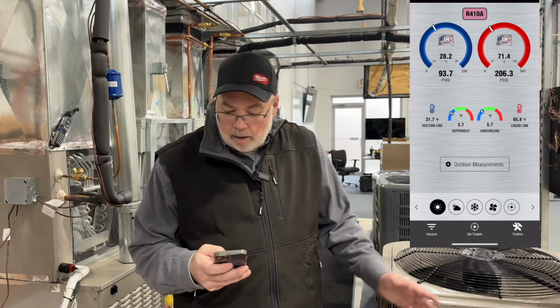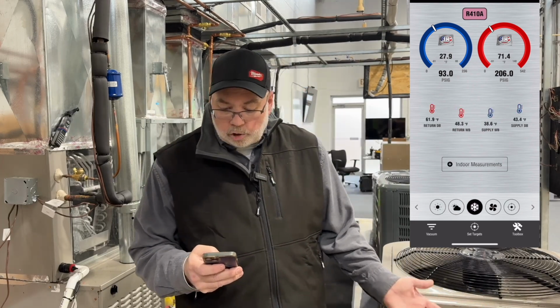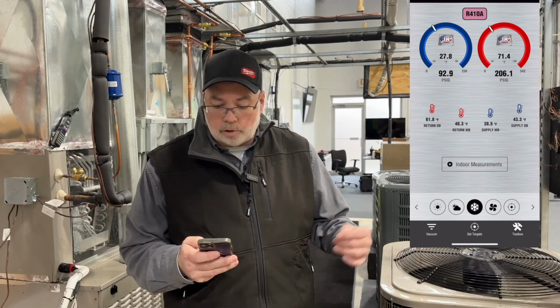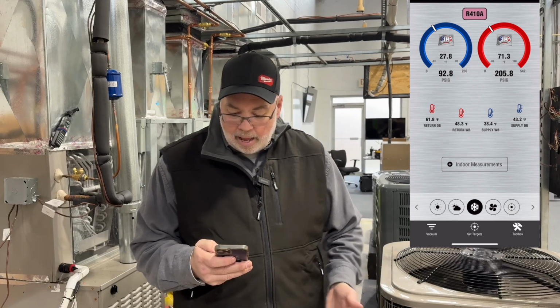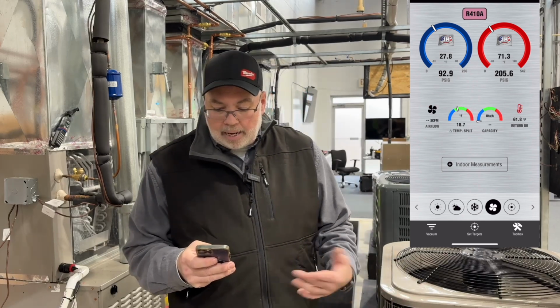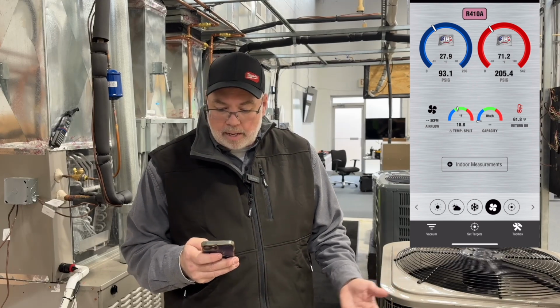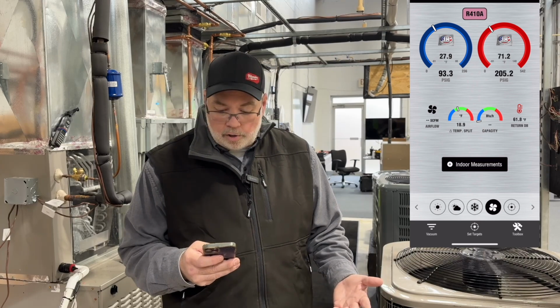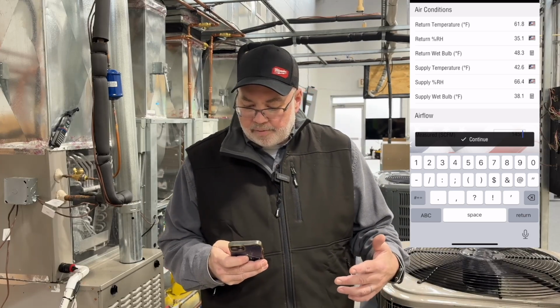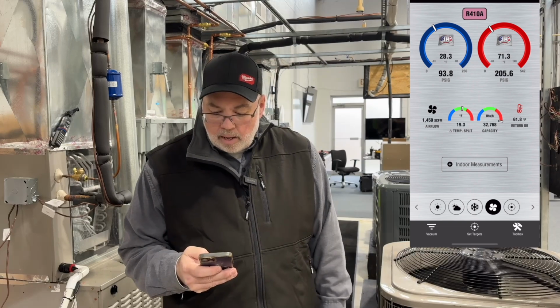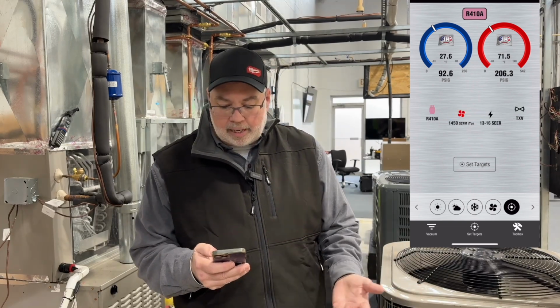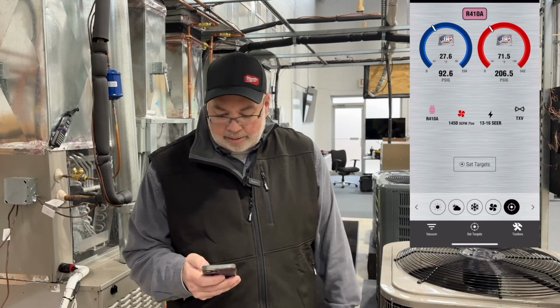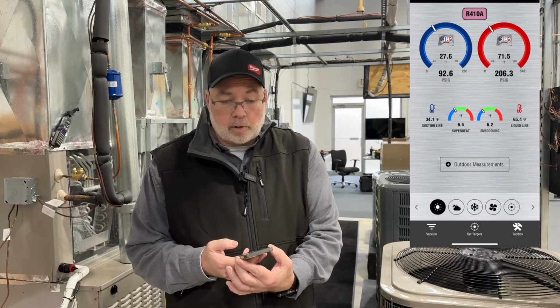And so we see our outdoor readings. We scroll through and we can see our indoor readings, our dry bulb and wet bulb on both supply and return. Now, it actually shows us our delta. It shows our temperature split. And if we enter airflow, which I'm going to do now, I remember the airflow here is about 1450. I'm just going to plug that in. And now it actually tells us what our capacity is. Now, it's actually a 14 SEER unit, so we chose 14 to 16 SEER with a TXV. And so it's a nice little app that gives you all the information.